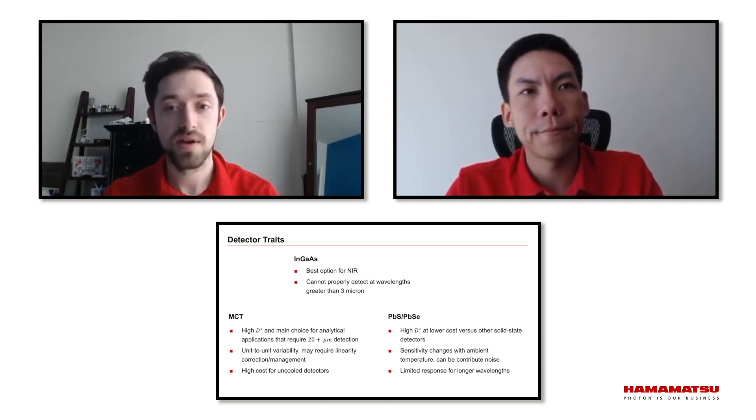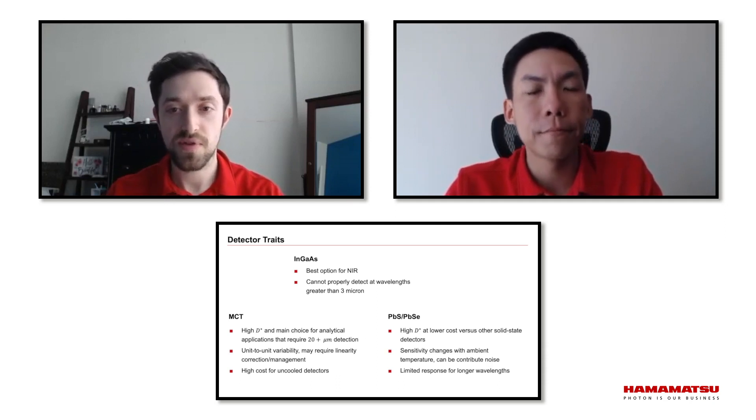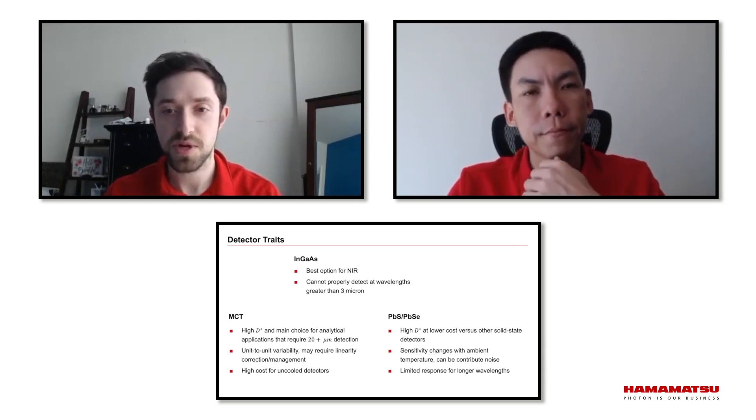Mercury cadmium telluride, a very popular choice in FTIR applications since it can reach very long wavelengths and it's highly sensitive. However, the nature of the material with its spatial sensitivities and fluctuating D-star unit-to-unit dynamic range can be limited.